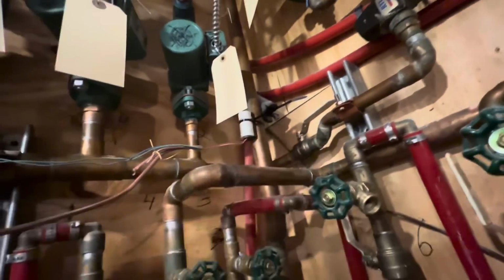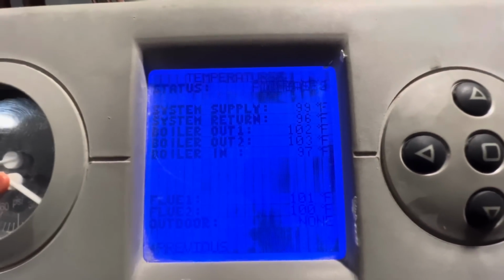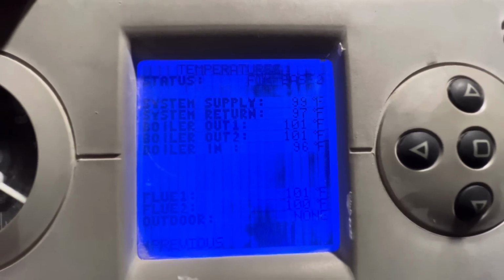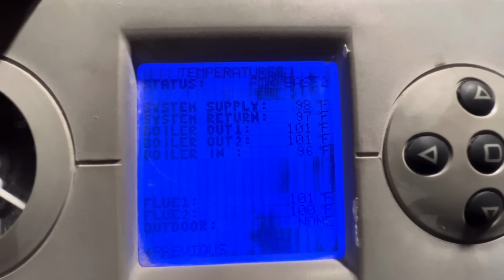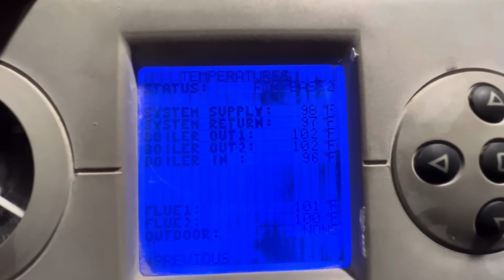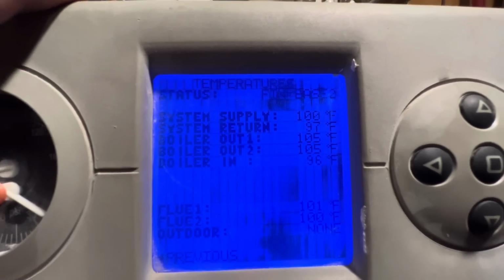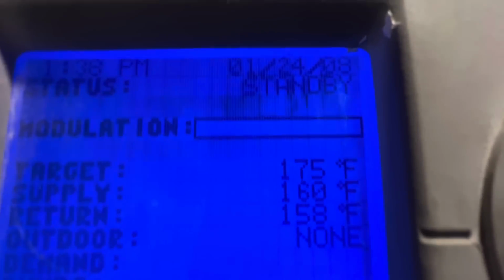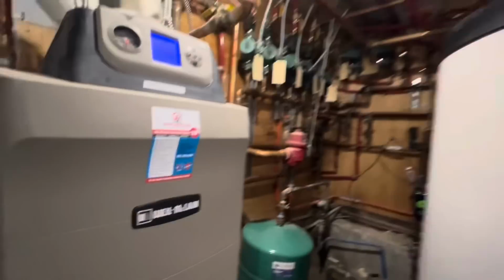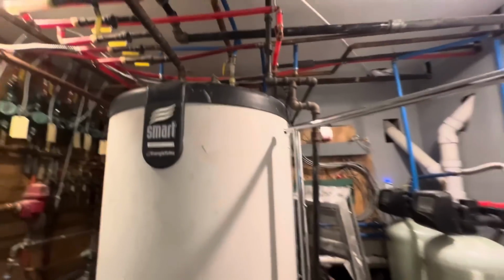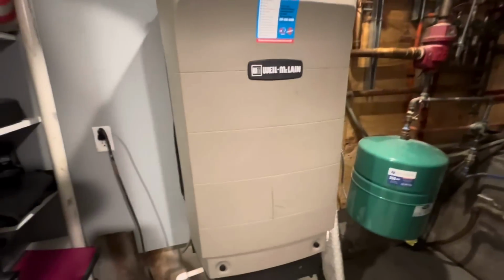I shut the system down for a minute because I moved our supply sensor to our supply line, which was originally right here, and I moved our return sensor, which was right here, to our return line up here. So we should get better, more sensible readings now. Maybe they're closer to the boiler temperature already. Just hit standby on our hard to read display, so we're all good to go here. Working for domestic and space heating, and we satisfied, so nice. Okay, so I finished up.